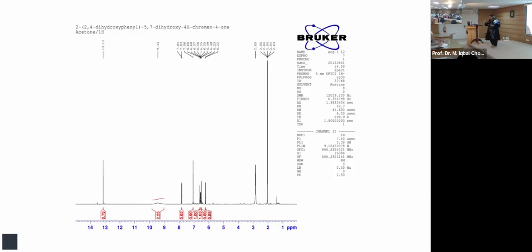But usually when we have a longer NMR experiment, we would like to have some dummy scans, like 8 or 16 or 32. Longer experiments actually go for days. Specifically when we are running 3D NMR, we would sometimes have 64 and 128 dummy scans.